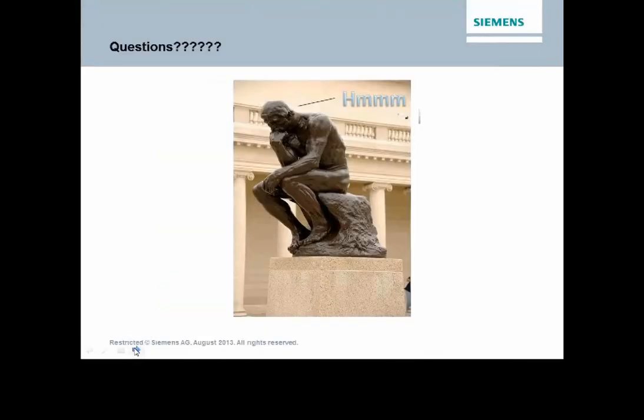We have a question. Can we go back to your illustration of the use of a stilling well? Sure. The question is, if you're going to use a stilling well, what's the minimum stilling well size to get a good reading? The general rule is you match the size of the flange with the size of your stilling well, so that the stilling well acts as a wave guide. In this case, with the hygienic 2-inch, I would want to use a 2-inch stilling well. But when it comes to stilling well applications, we basically want to use the largest size available. So they don't recommend using the 2-inch size with stilling wells, but match the stilling well diameter with the flange size.